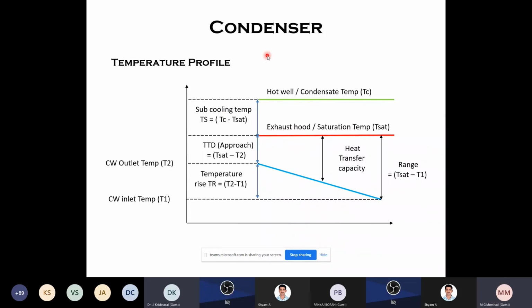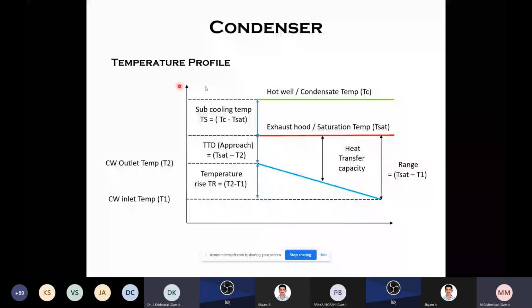Basically, for condenser performance, we are worried about the condensers only for the vacuum loss. We do not know for what reason the vacuum is lost. If vacuum loss takes place, automatically the performance of the unit also goes down. So we have to identify where the vacuum loss is and what the reason behind it is. For that, this temperature profile should be there.